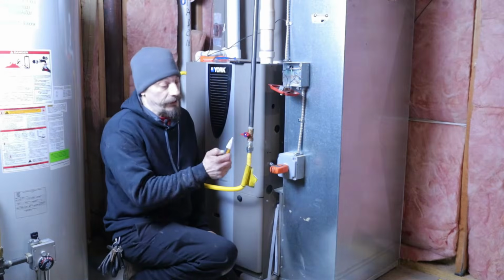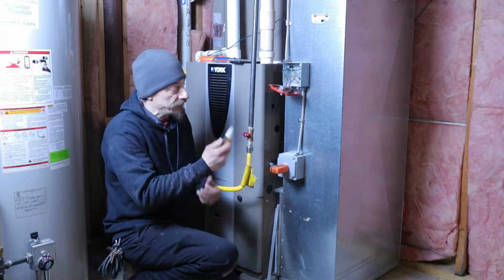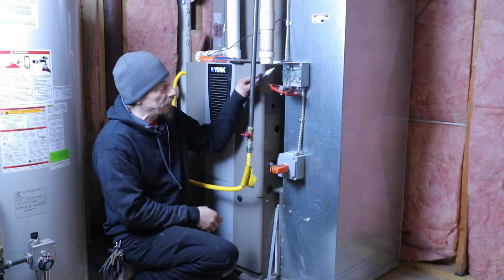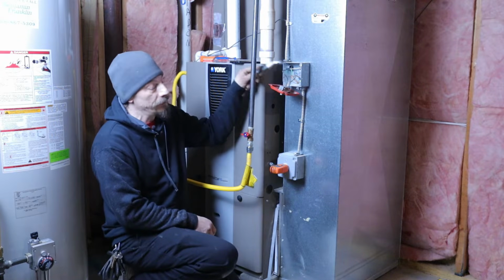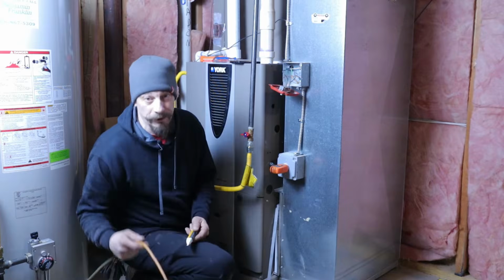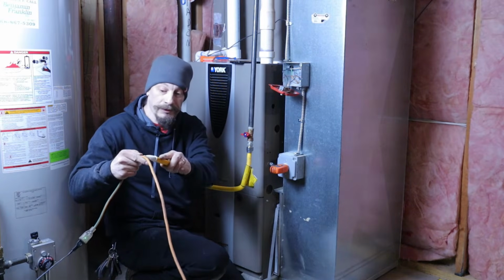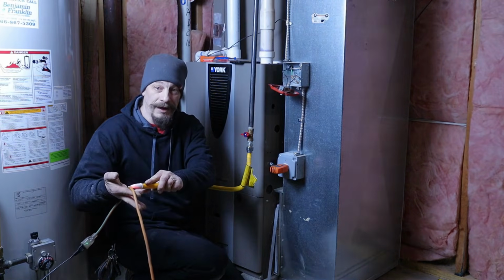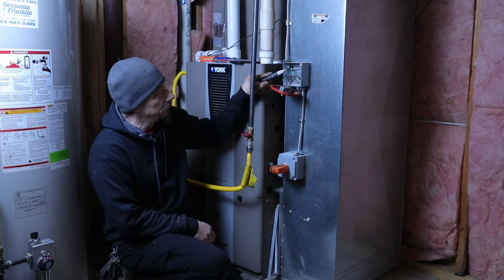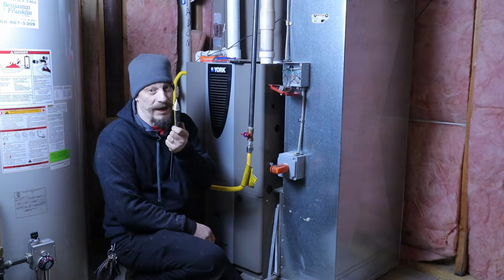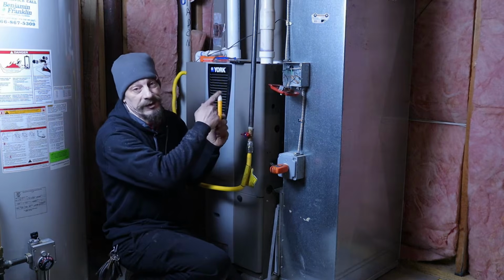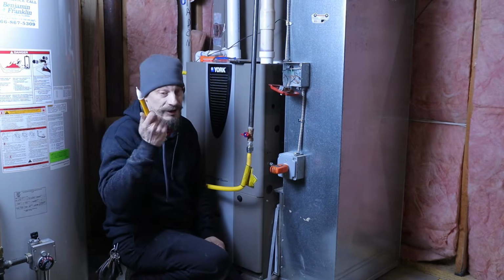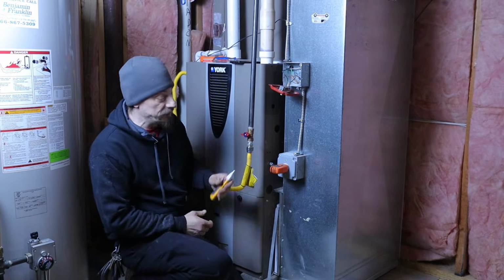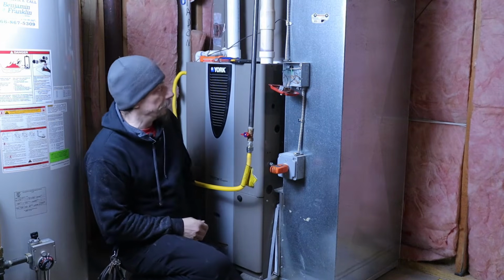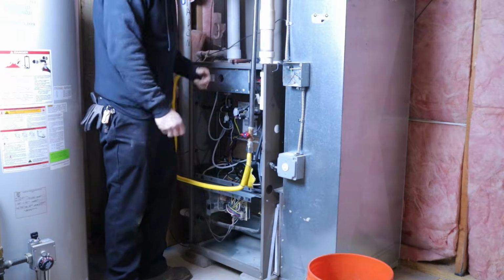Another thing you can do with verifying the electric, it's basically called a 3-point test. When you test for power and you have no power there, you can always go to another live wire, like an extension cord like this. And I have power there, go back. That's basically testing the pen. So what we did before was we tested to make sure we have the right breaker, and now I was testing the pen. So just keeping things safe. And now we're ready to start tearing into this.